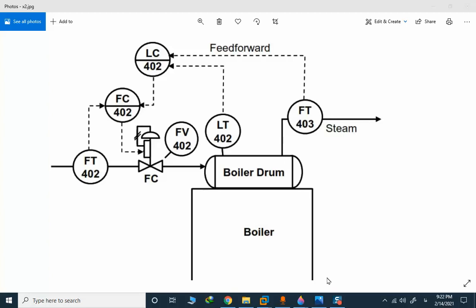We are back with the feedforward application in a drum boiler drum control. In this structure you can see that we have a cascade control — the LC level control is the master control, and the feed water flow control is the slave control. We use the output of the steam flow transmitter as a feedforward signal for the main master controller. I created a very simple simulation.